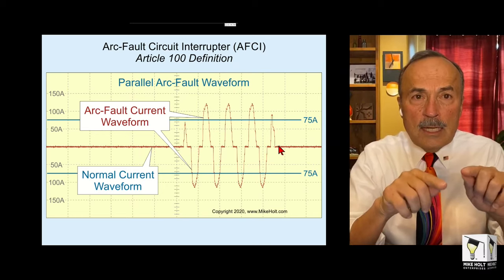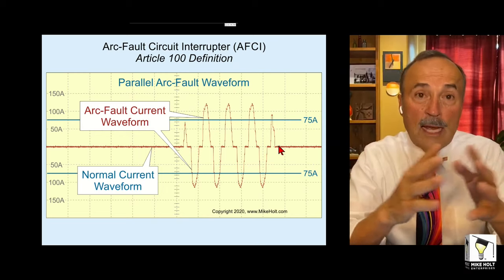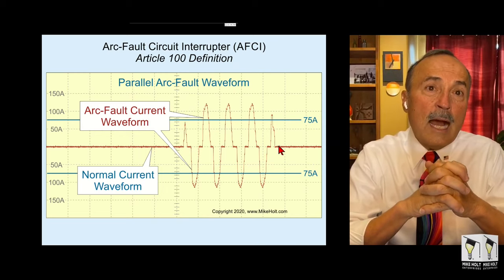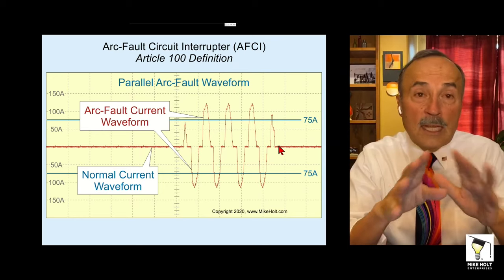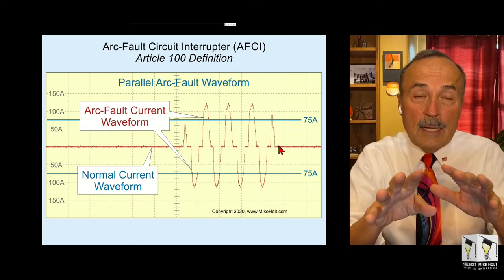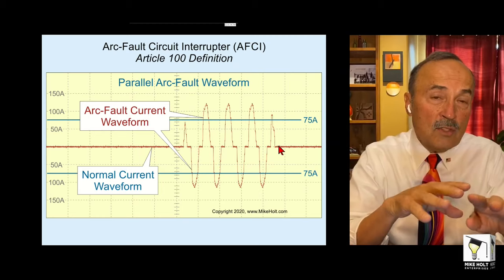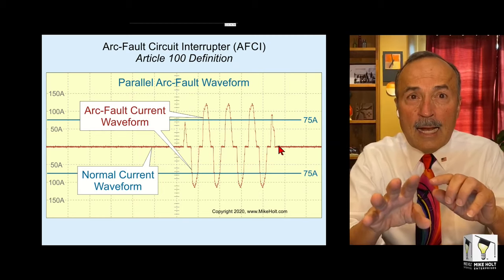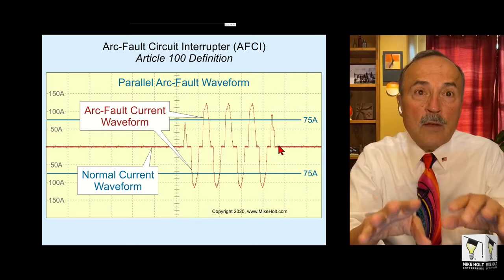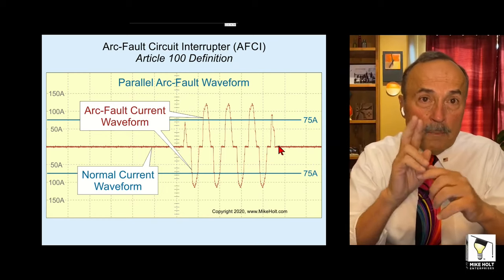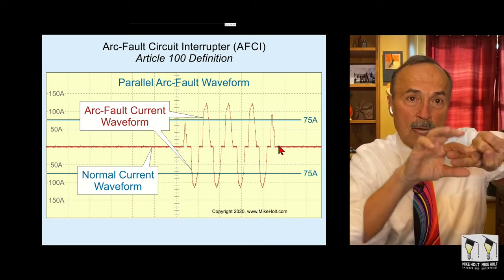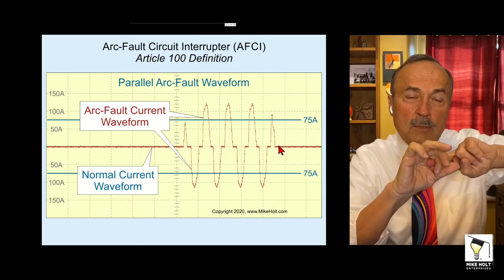The AFCIs today, well, not today, for the last few code cycles anyhow, they're combination AFCIs. Now, don't misunderstand the word combination AFCI to be a combination GFCI AFCI. A combination AFCI is looking for an arcing fault that's parallel, that's hot and neutral, kind of with a cord smushed or something like that.